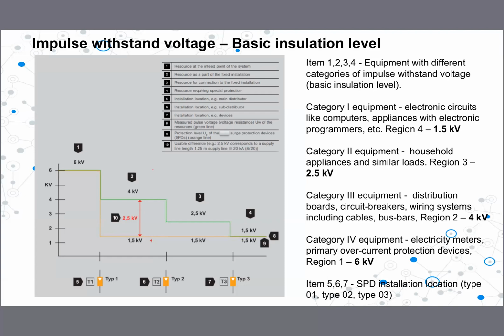Yeah, when there is a transient voltage, a high voltage spike, at the same time there can be high current as well, right? So therefore, your SPD should be able to handle both, not only one, right? When a transient voltage happens, for example, with a direct lightning strike, your voltage level is 6,000 or whatever, and at the same time the discharge current through the line is in kiloamperes. Therefore, when you select an SPD, you need to look at both. So that's why you need to find the correct kiloampere level for the particular SPD.